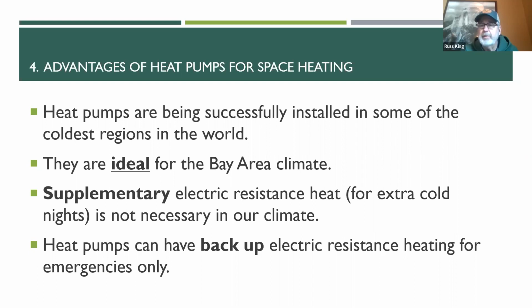Now, a lot of people are concerned, what if the heat pump doesn't keep up for some reason? In a lot of places, they will put electric resistance backup strips or supplementary heating on there for extra cold nights. That's not needed in our climate. Heat pump electric resistance strips are not necessary in our climate. You can put them on for emergencies, but they shouldn't be a supplemental heat. The heating capacity of the heat pump by itself will handle the heating load of the house. But if you properly size your heat pump, the heat strips should never run.